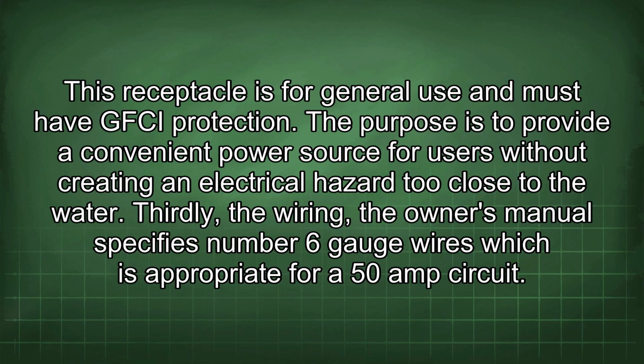This receptacle is for general use and must have GFCI protection. The purpose is to provide a convenient power source for users without creating an electrical hazard too close to the water. Thirdly, the wiring. The owner's manual specifies number 6 gauge wires, which is appropriate for a 50 amp circuit.